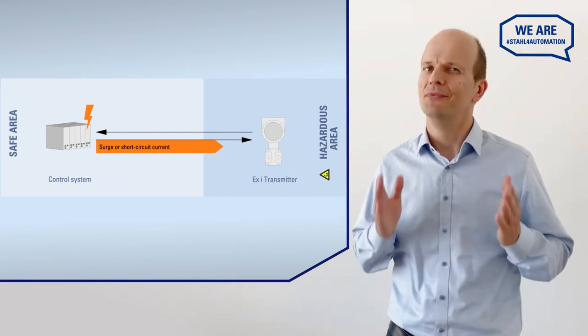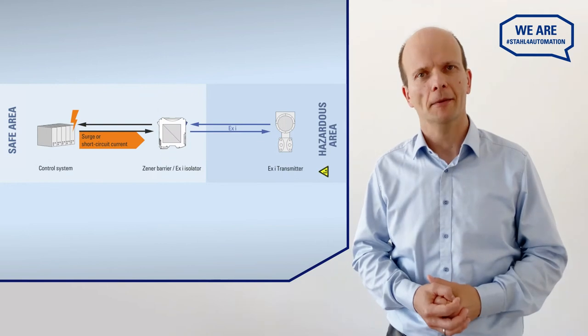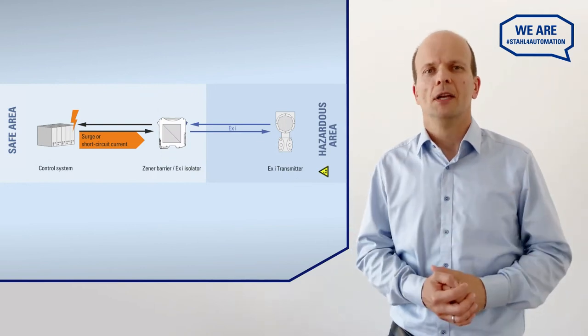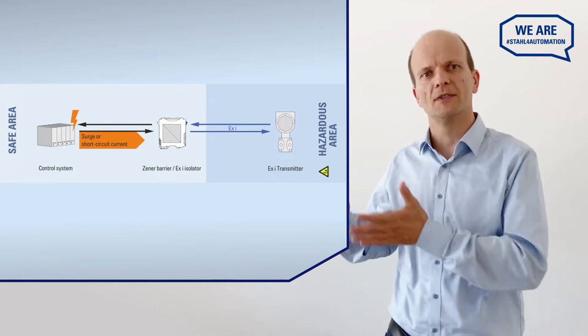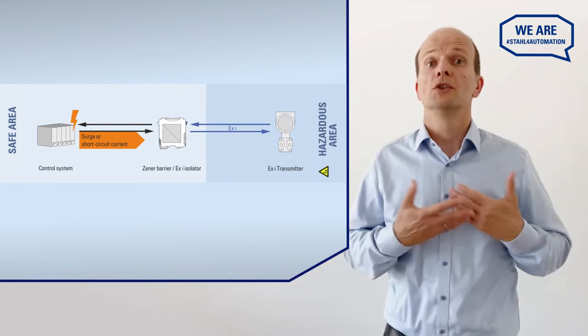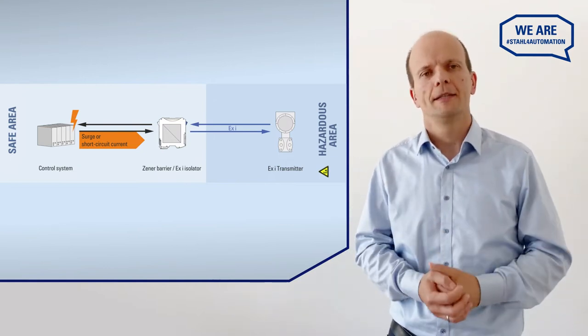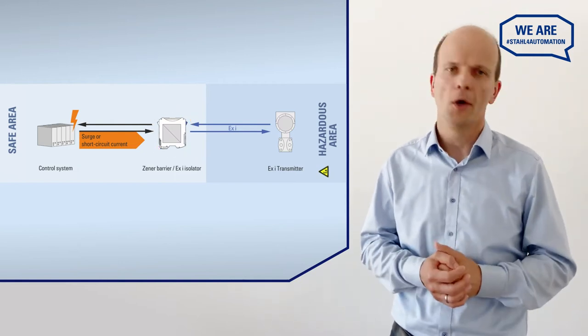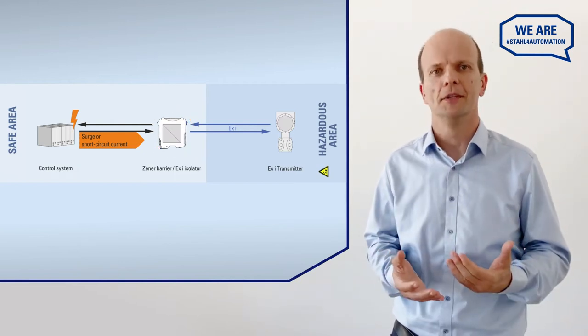That's where the barriers and isolators come in. These devices separate circuits that are intrinsically safe from the ones that aren't, which ensures that events like a surge or a short circuit will not impact the intrinsic safety.